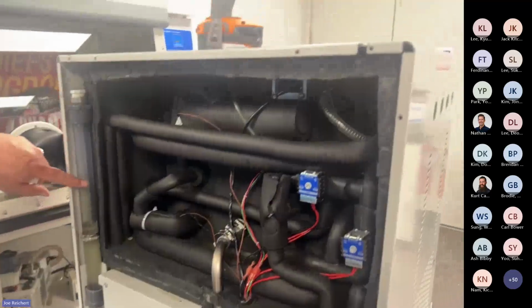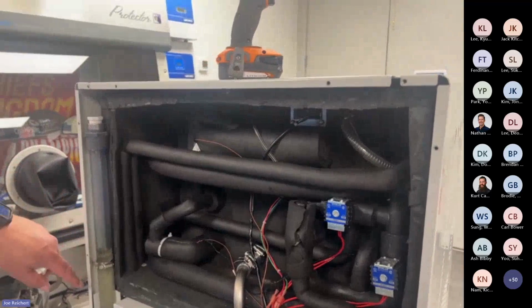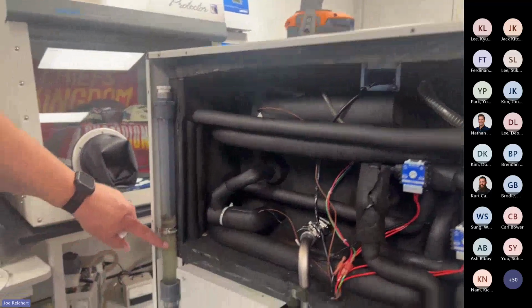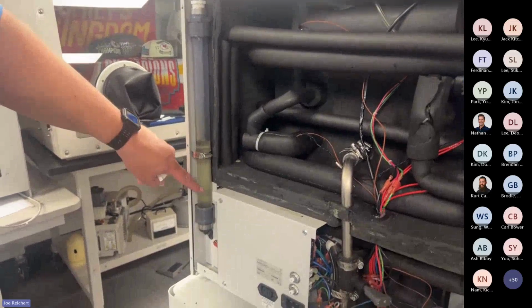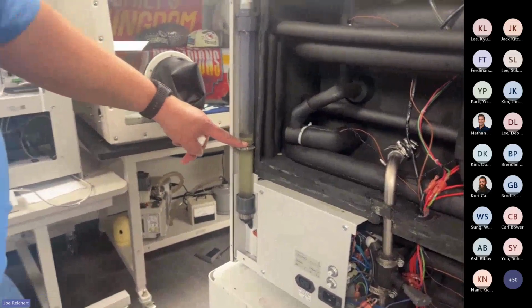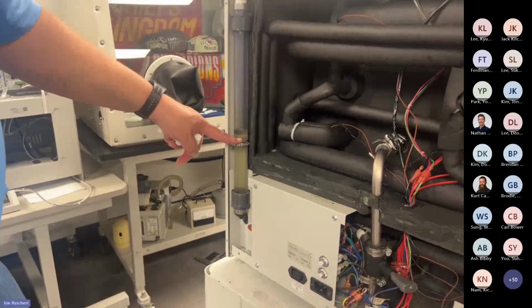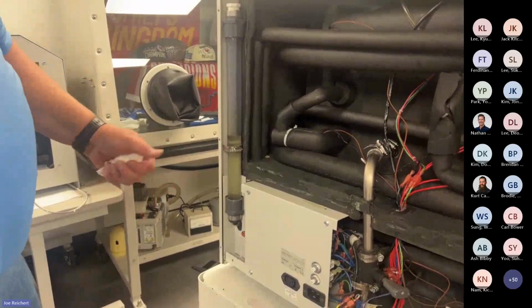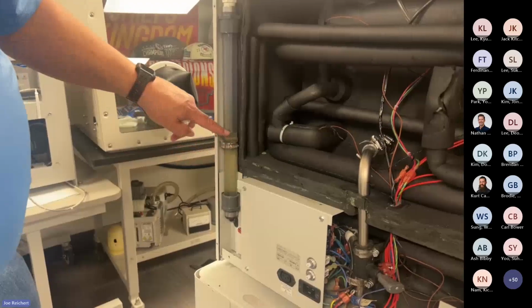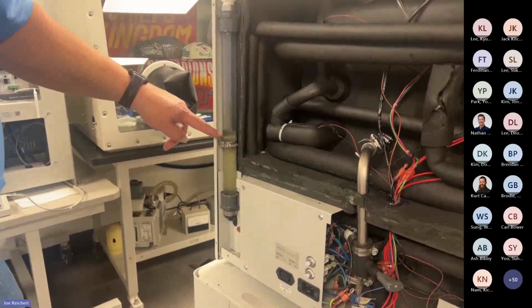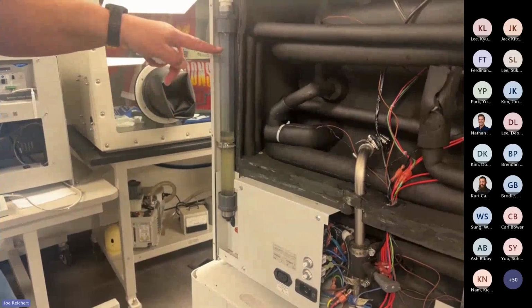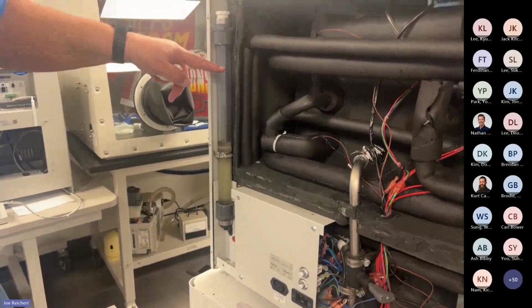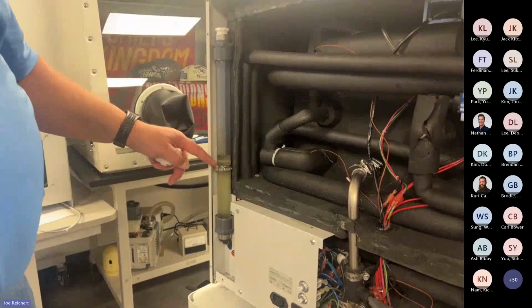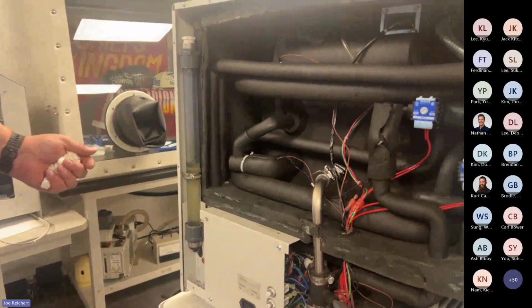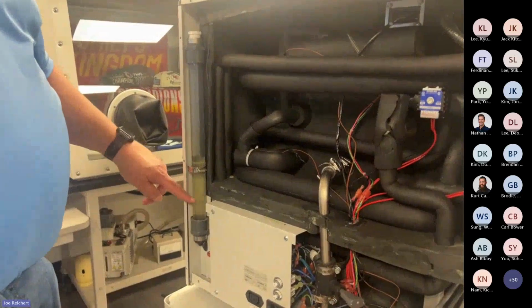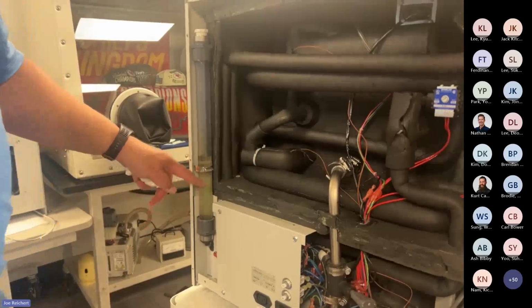Then you have your Lexol tank along the side. Normally this has a pink color to it, but this unit has had some age. We put pink in the Lexol so that it can fluoresce whenever you shine a black light on it, and it'll glow like a light green. Your Lexol level, even though this is only halfway down, is not a bad level. Normally it is filled all the way to the top. But if it's down here, it's not physically using this fluid during the system unless you have a leak someplace. Lexol has a bad odor to it, so it's easy to smell.